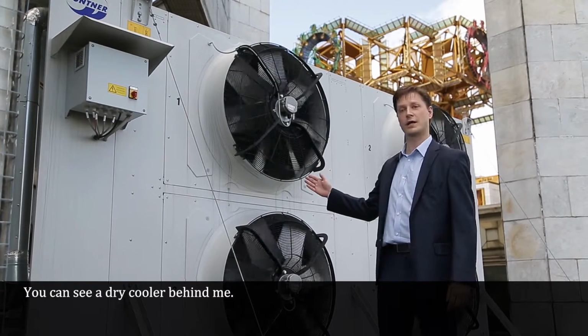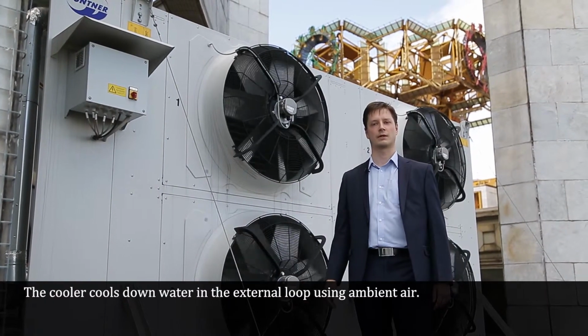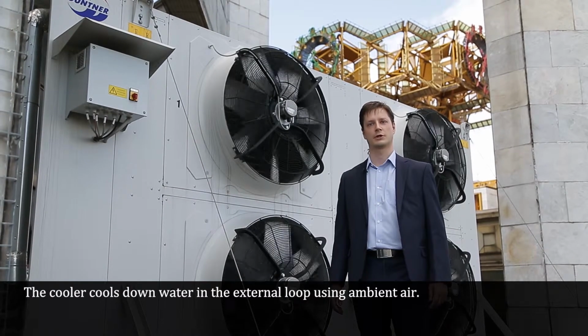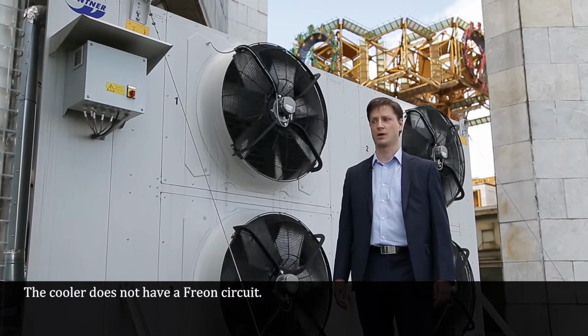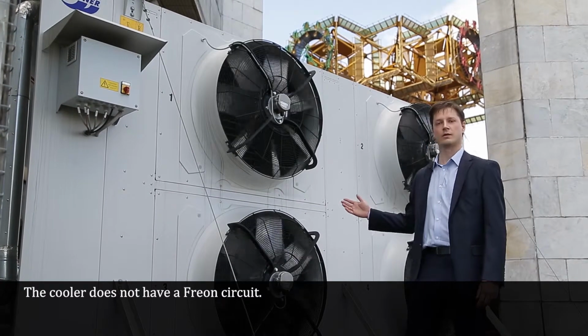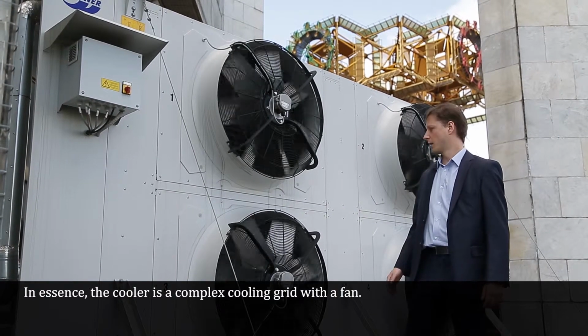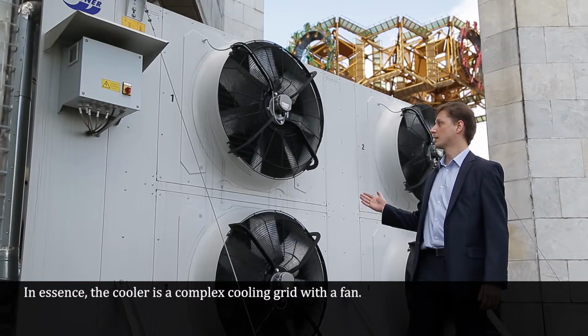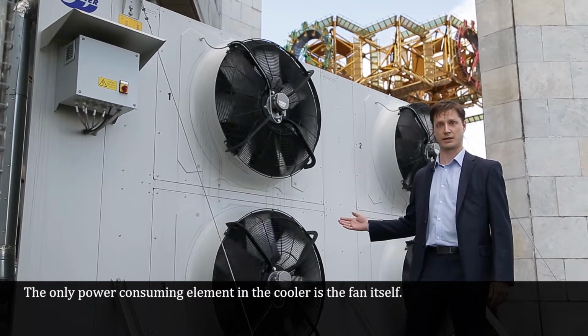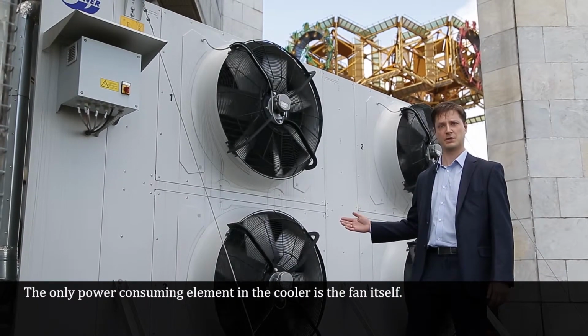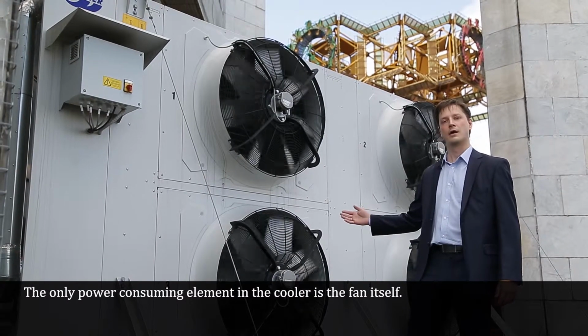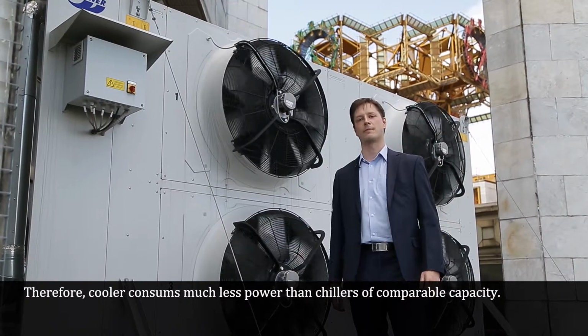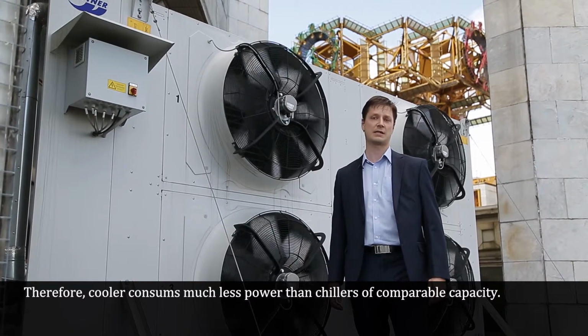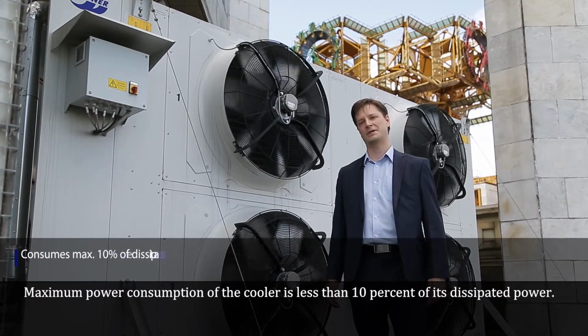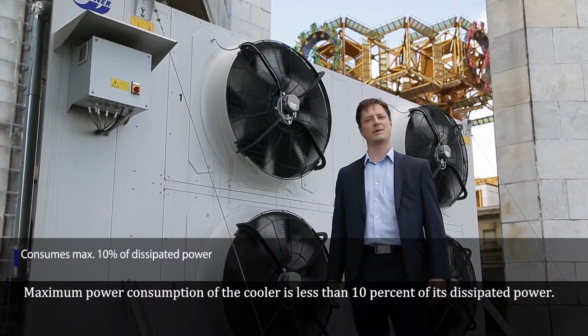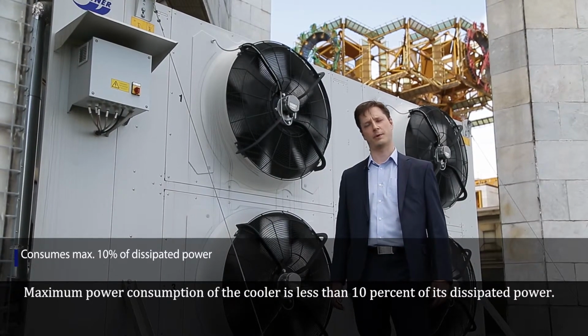You can see a dry cooler behind me. The cooler cools the water down in the external loop using ambient air. The cooler does not have a freon circuit. In essence, the cooler is a complex cooling grid with a fan. The only power-consuming element in the cooler is the fan itself. Therefore, the cooler consumes much less power than chillers of comparable capacity. Maximum power consumption of the cooler is less than 10% of its dissipated power.